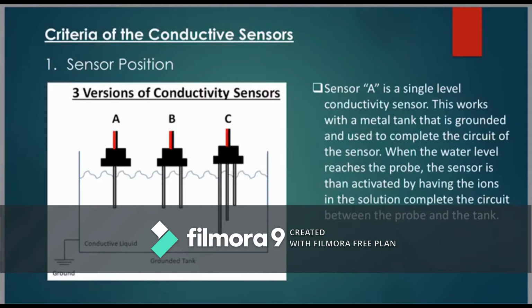Sensor position. There are three versions of conductive sensor. Firstly, we have sensor A. It's a single level conductivity sensor. This works with a metal tank that is grounded and used to complete the circuit of the sensor. When the water level reaches the probe, the sensor is then activated by having the ions in the solution complete the circuit between the probe and the tank.